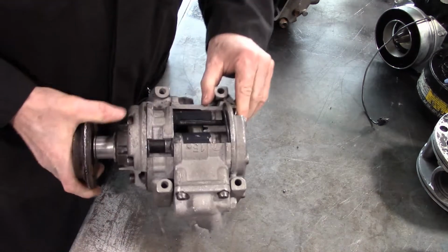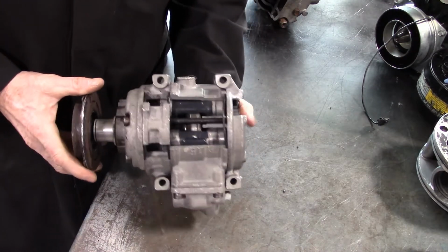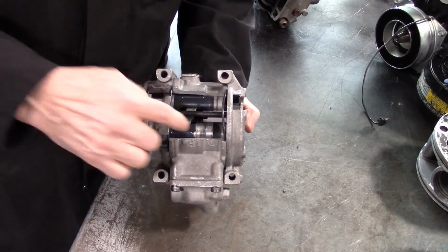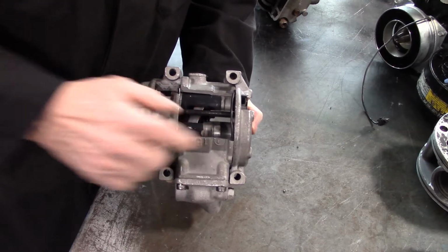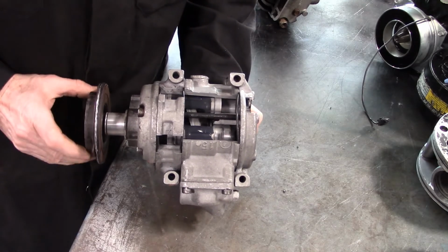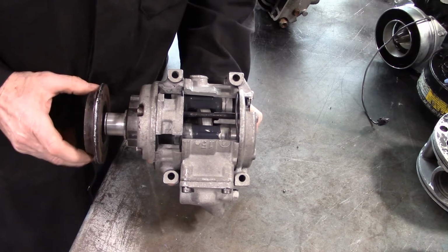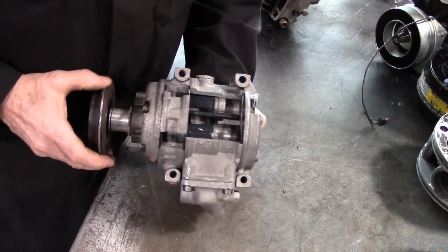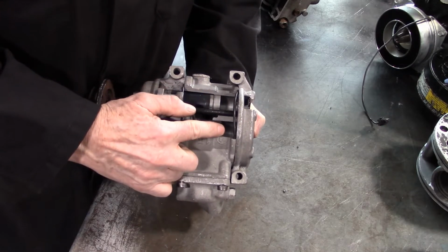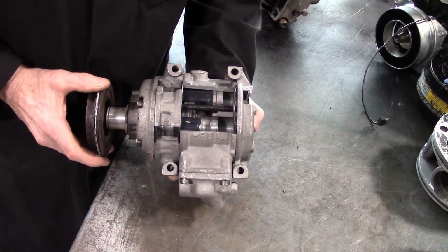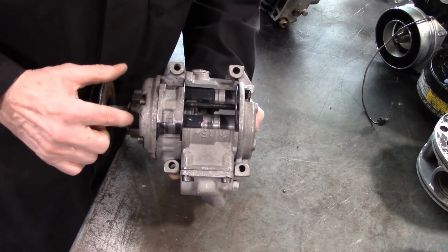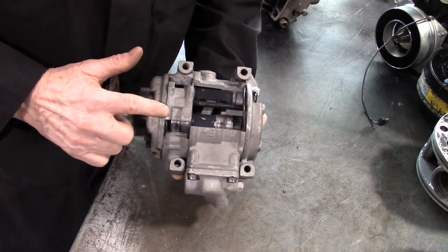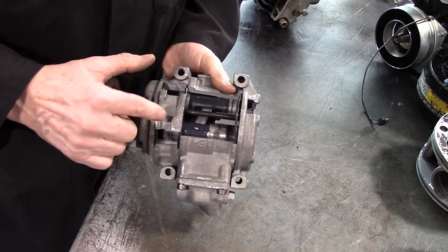This is slightly different, and I hope everybody can pick this up on the video. This is a swash plate. On this one, we have double-ended pistons. So as I turn it, you can see the pistons moving back and forth, but they are designed with valves on each end so that as one piston is moving back, it is drawing in refrigerant here, and then when it gets to the bottom, it stops and goes the other way, and it's pushing refrigerant out here now, but it's also drawing refrigerant in on this side as well.